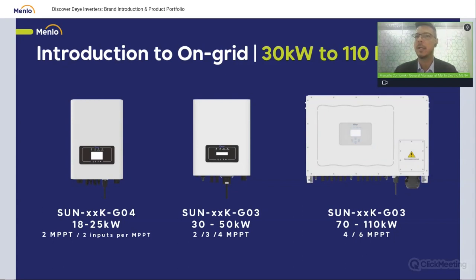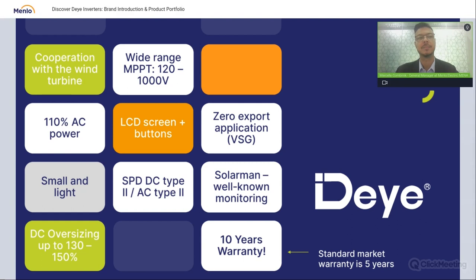Looking at the big 110 kilowatt, the market normally has 12 or 10 MPPTs with 2 inputs, but this inverter topology is a bit different — they've got 6 MPPTs with 4 inputs, meaning the MPPT amperage is also higher than the standard market focus. This is something we'll discuss in more detail during our on-grid technical webinar.